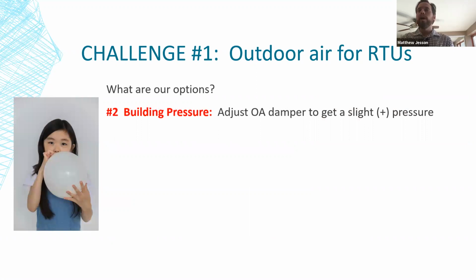So what other options do we have if you can't do the arithmetic version? One is to try it by building pressure. Blow up the building like a balloon, by which I mean you just adjust that outdoor air damper until you get the building to be a slightly positive pressure, if that's the typical goal.